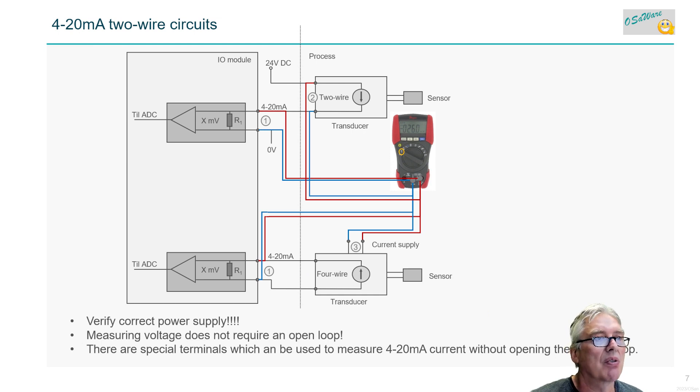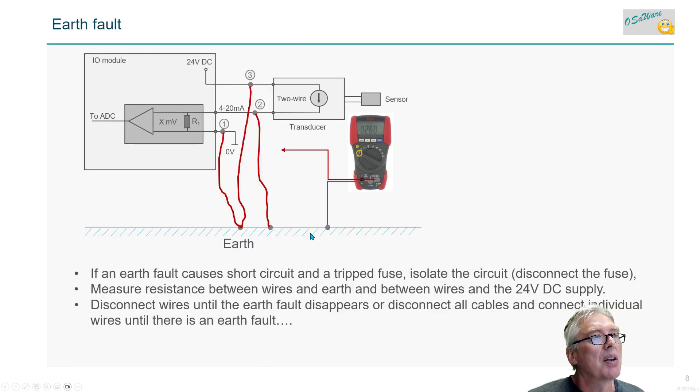Looking at earth faults - if you have those, you often get noise into your system, so you have to locate those. Measure voltage to earth. Maybe the fuse has tripped - disconnect the fuse and try to measure resistance between the earth and your wires. Maybe you can use the buzzer too if you're disconnected here.